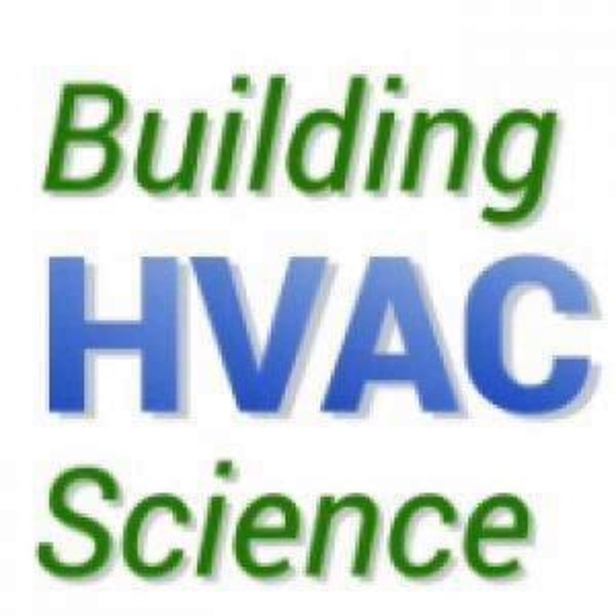And at the end of the day, efficiency-wise, in terms of the electrical consumption of our units, when you compare all the things those units do, we are extremely efficient, because a common mistake is to compare us strictly to a regular HRV, ERV, and a ductless split air source heat pump. But the quantity of moisture removed with those units, to do that same amount of work, I should say, you would need a standalone dehumidifier. Either one with a bucket or a great machine like a Santa Fe or something like that.